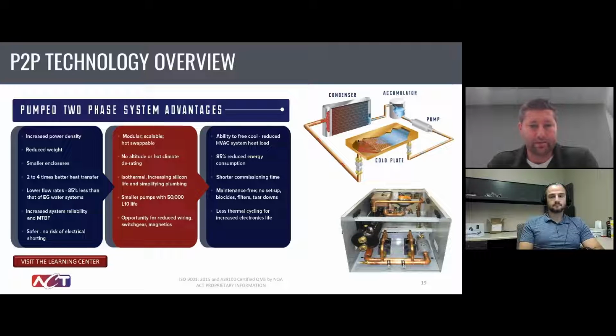There are a lot of benefits we're showing here, and I'll couple on some of them. Again, the intrinsic safety with the dielectric working fluid. One of the biggest concerns of a water-based liquid solution is if you do spring a leak, you are going to damage all your electronics and have to start from scratch. In these systems, you're actually not using a ton of fluid because you're running at two-phase, again taking advantage of the latent heat of vaporization. If you do have a leak, it'll dispel refrigerant in vapor form, it's dielectric so it won't damage your electronics, and you'll have ways to monitor the system so that you can safely shut down and save all the electronics and just fix the leak and go from there.